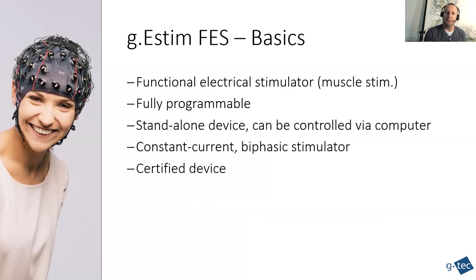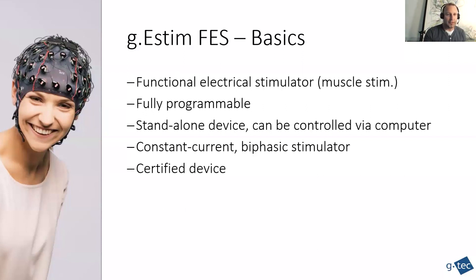You can fully program it, but you can also run it as a standalone device. There is also software provided with the g.Estim FES that you install on a Windows computer, and you don't need any MATLAB or Simulink to control it. But for closed-loop experiments, we need more analysis steps before. It's a biphasic stimulator and also a medically certified device because we also use it for rehabilitation, for example.